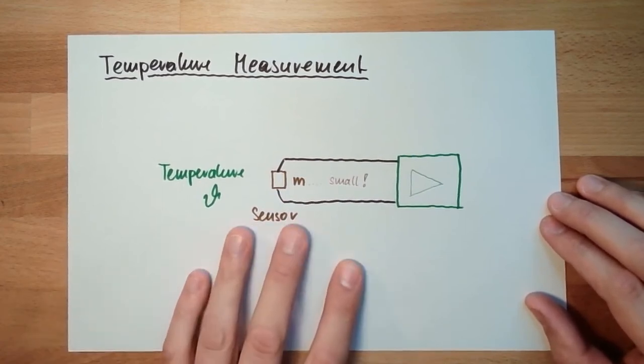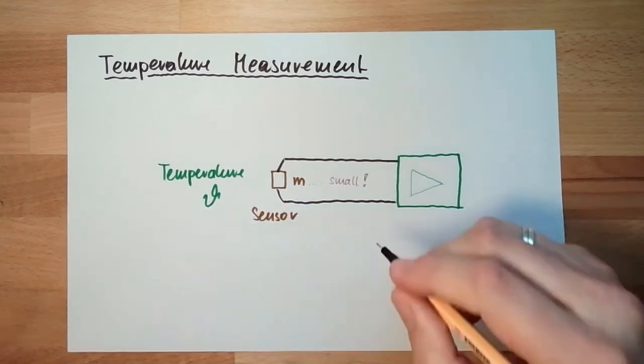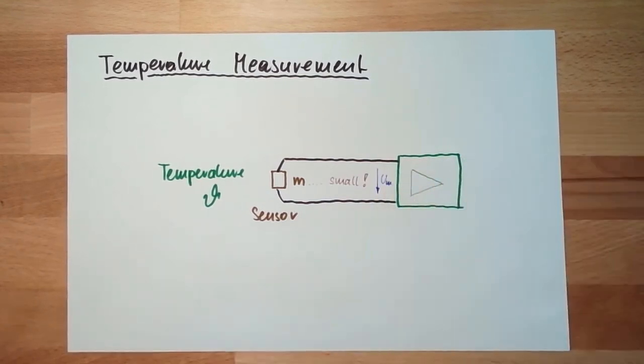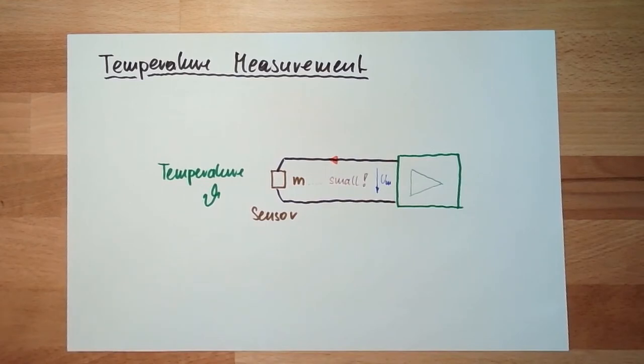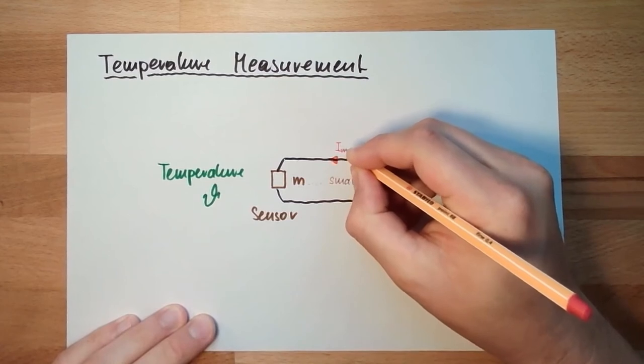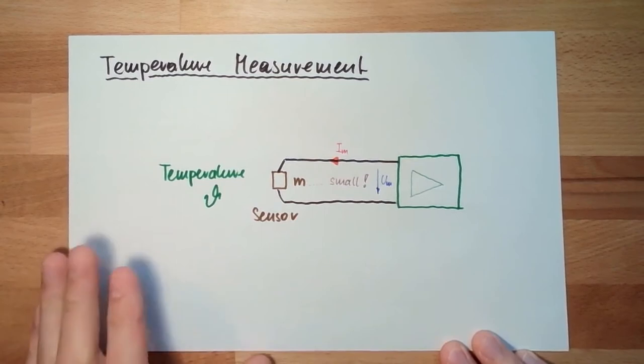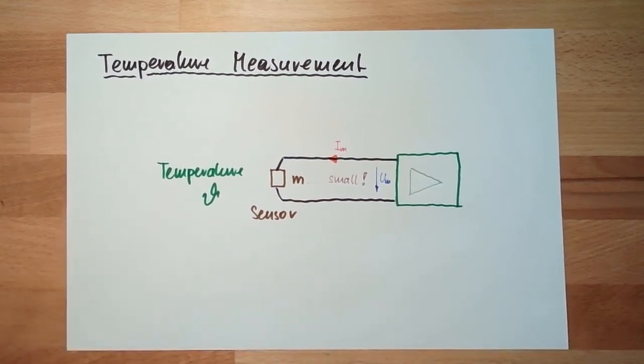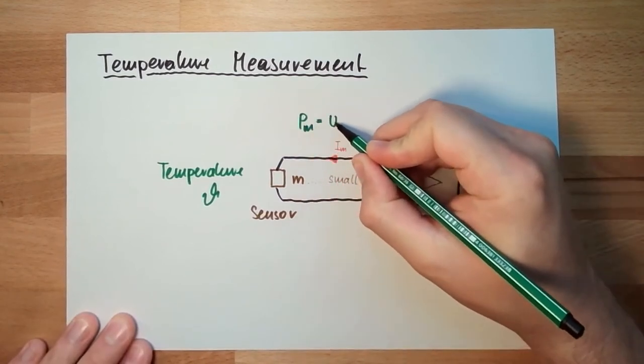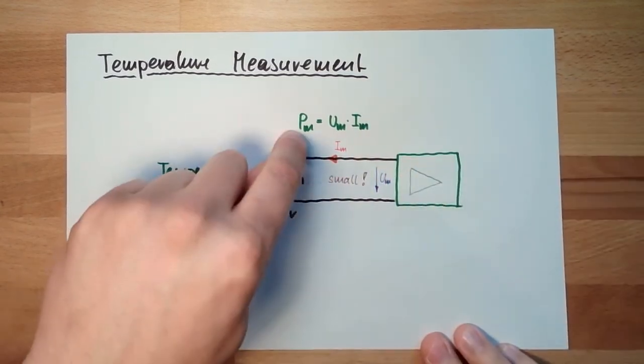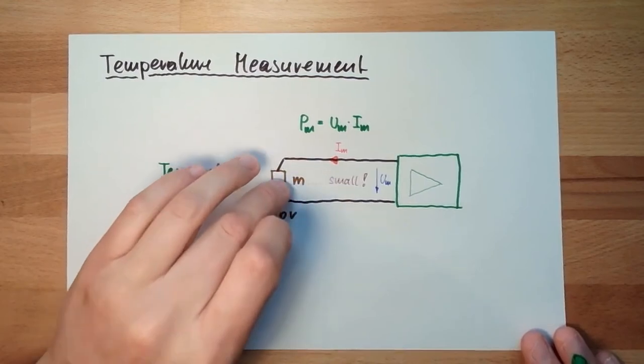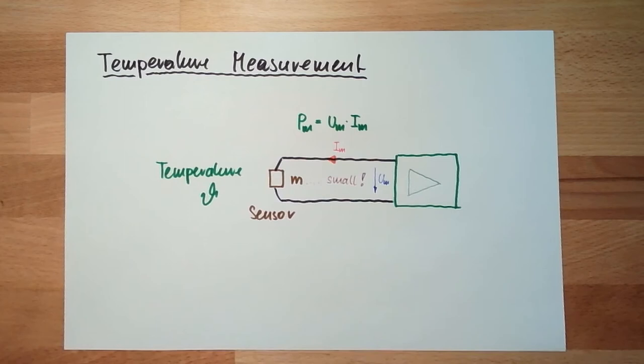That's one thing, the mass of the temperature. The other thing is, usually we do have here some voltage, measure voltage, and we do have here some current, measurement current. Whenever we have voltage and current somewhere, whenever we have this, we do have also power. So the power, the measurement power of the sensor is the voltage multiplied by the current. This power is brought into the system. There is some self-warming of the sensor, just because we connected it electrically. The sensor is getting warmer. Self-warming effect. Now it depends a little, how much does this influence my measurement?